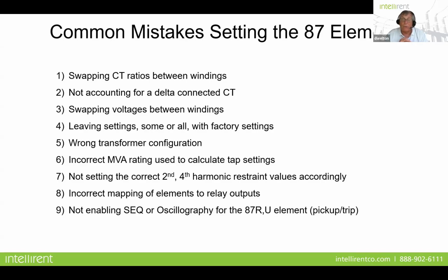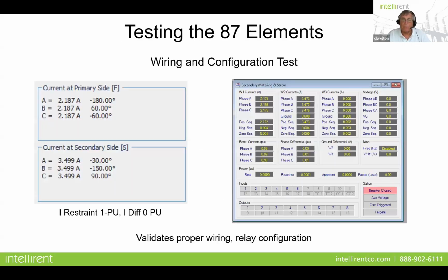Incorrect mapping of elements to relay outputs. And this is a big one that you can get into trouble with, especially with the Schweitzers, because they're a little bit more complex. You have to make sure that not only do you activate that element, but you map it out to the correct contact as well. And the big one, not enabling your sequence of events or your oscillography for any of the elements, not just for the 87. And that's very, very important. That oscillography is going to help you with your analysis in the event that something happens.